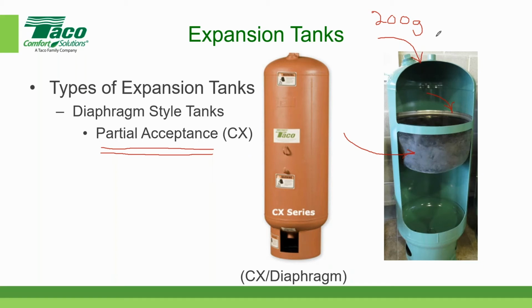And by the way, in terms of adding air, this top part of the tank here is the air side. There's the collar that protects the Schrader valve, and the Schrader valve I showed you in the previous slide is the same thing. So that's where the air goes. The water connects to the bottom. Actually, you can see over here, let's say I put an imaginary pipe over here that connects to the bottom of the tank, and that's where the water goes. So there's the water for that particular tank.